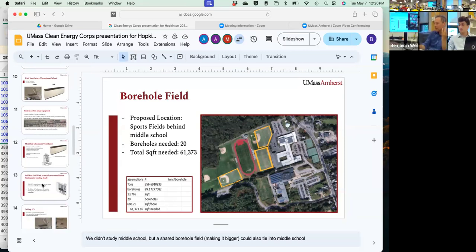I mean, to some degree, you've got a school that operates really well, right? You have a few events where it would be nice to have more capacity in the gym, right? This gives you more capacity in the gym. Essentially what I described with the ERV, making your coil bigger, right? That's what you're getting there. You can pack more people in there and provide sufficient cooling and fresh air. And you even have sometimes when there's insufficient heating in the gym, now you have more coil capable of doing that. You add cooling to all the spots.